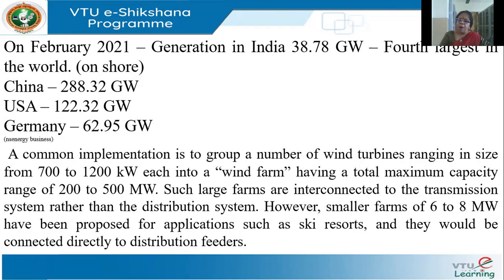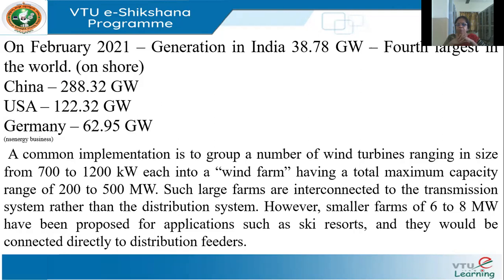Generally, a wind farm has a capacity of around 200 to 500 megawatts. Unlike a thermal plant where you can have one huge 500 MW turbine-alternator, that is not done with wind. Individual wind turbines are normally in the range of around 700 to 1200 kilowatts, and a number of them are aggregated into a wind farm to generate around 200 to 500 megawatts.